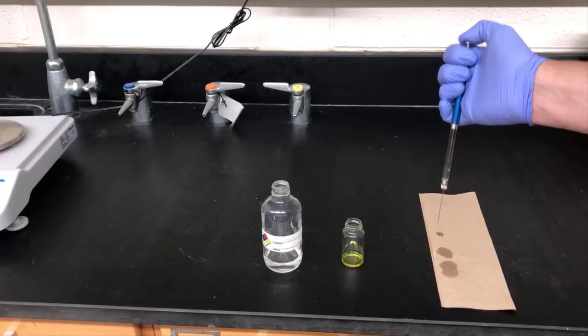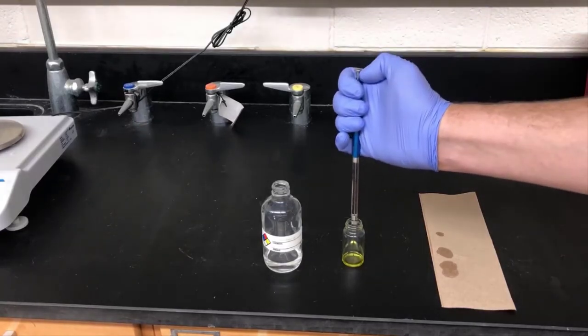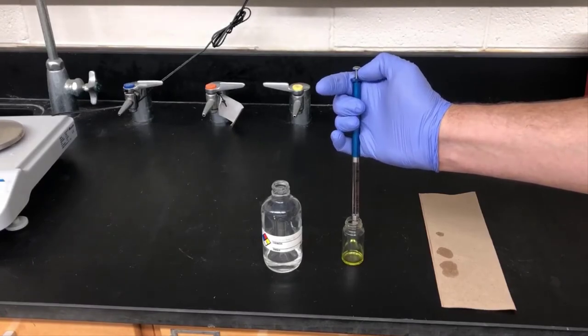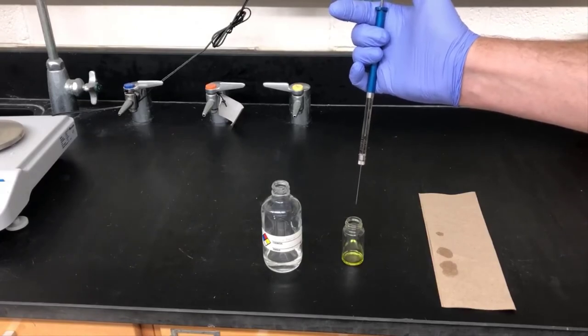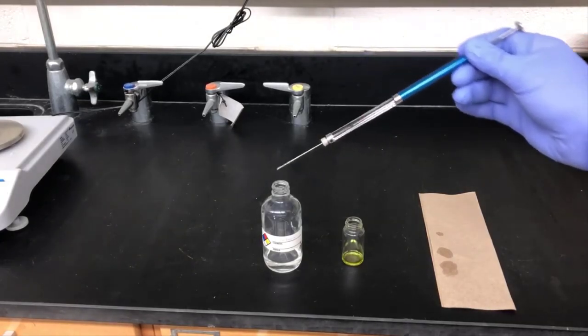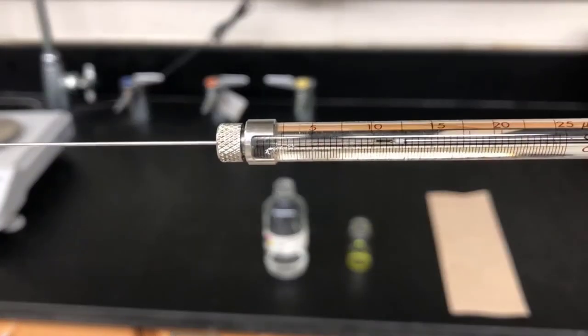The easiest way to do this is to stick the needle into the solution and pull back on the plunger about two millimeters. Then pull it out of the solution and pull back on the plunger to draw in about 10 microliters of air. Now I can look and see exactly how much sample I have in the syringe.